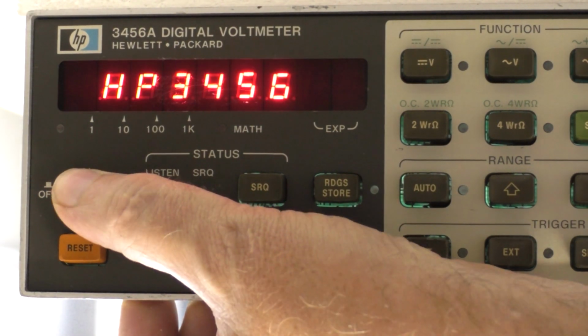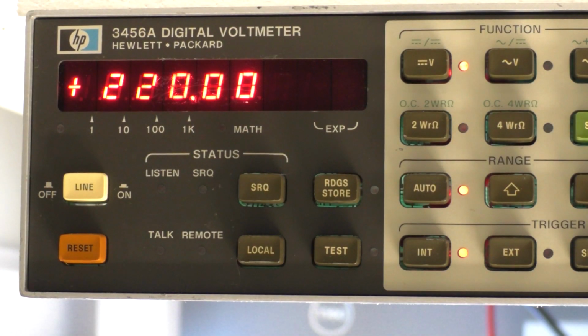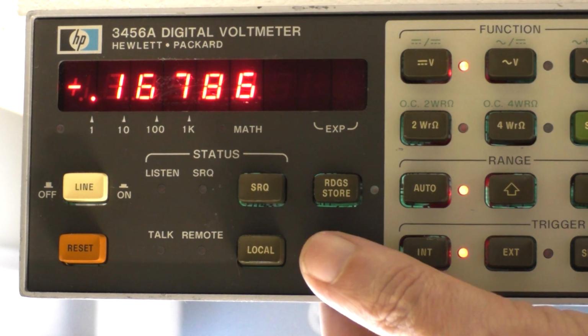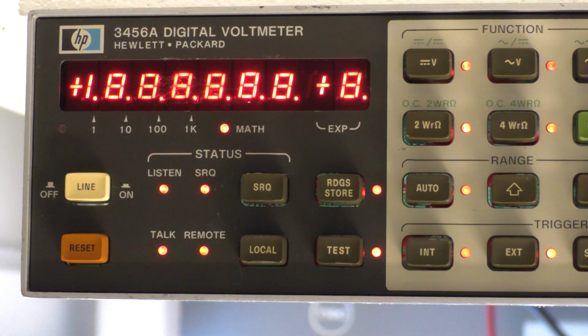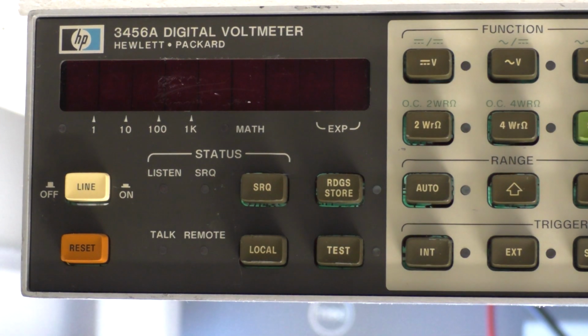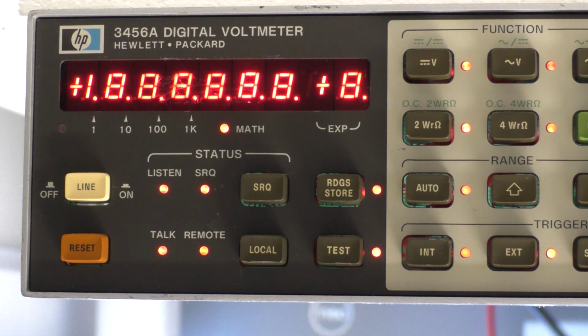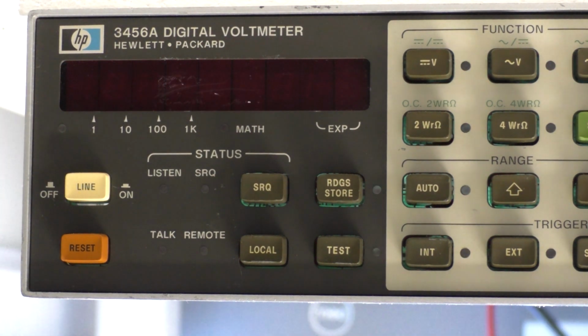Repower the machine. We note the overload has gone. Leave the machine running for a few minutes to see if the error returns. Hit the test button, again wait to see if errors return after some time. It looks like the issue has gone. Point 4 explains, if the instrument is now working correctly, the overload circuitry is at fault. This seems to be the issue.